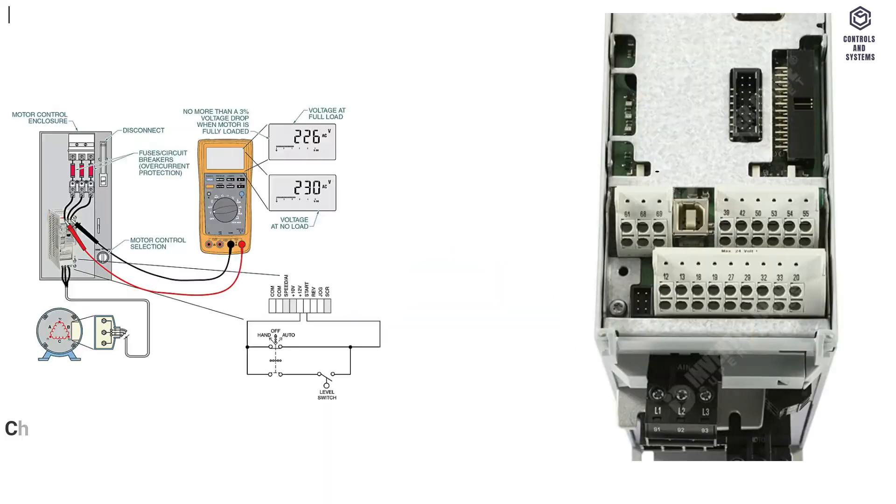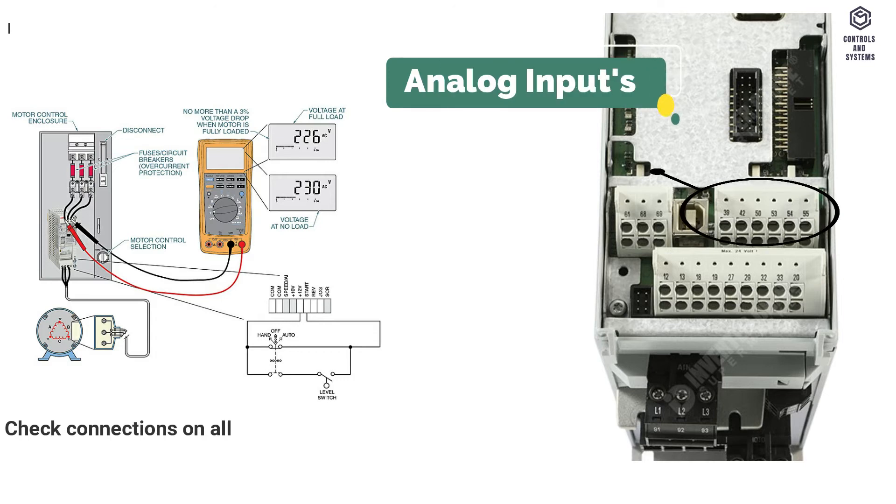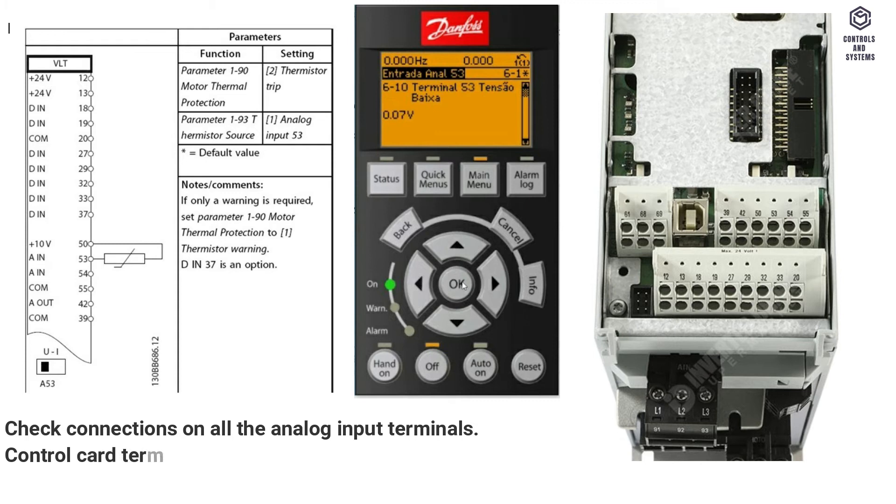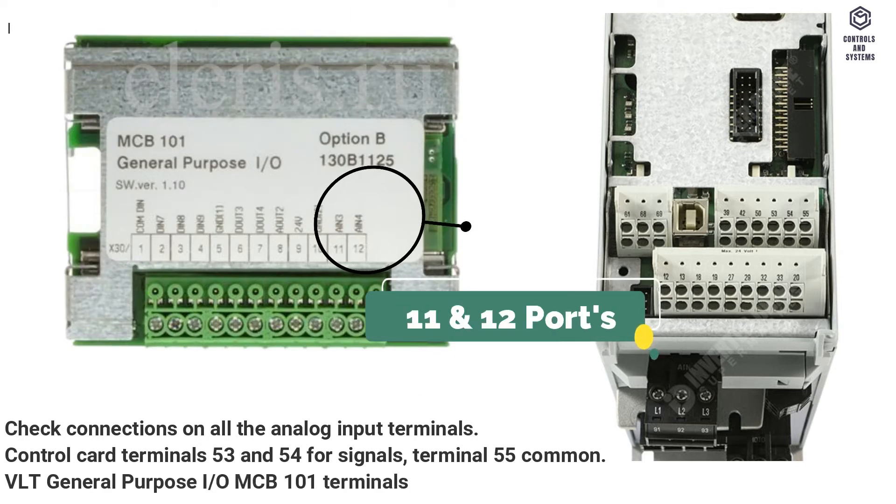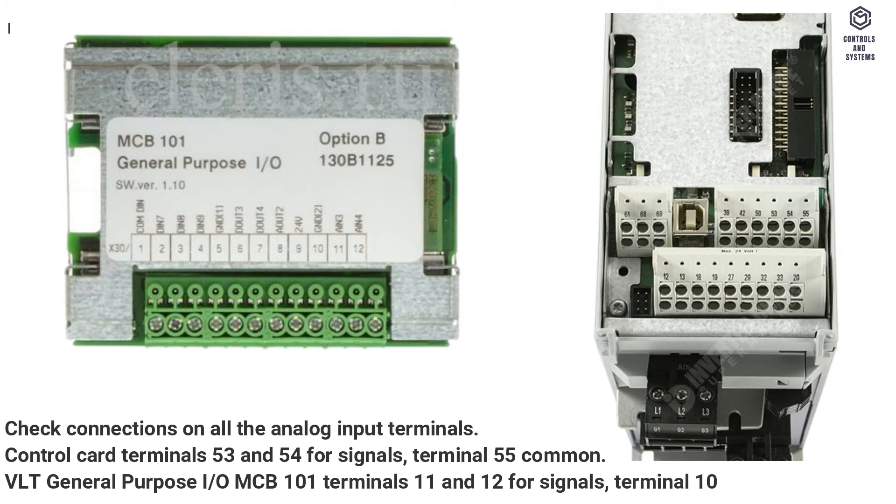Troubleshooting methods: Check connections on all the analog input terminals. Control card terminals 53 and 54 for signals, terminal 55 common. VLT general purpose I/O MCB 101 terminals 11 and 12 for signals, terminal 10 common.